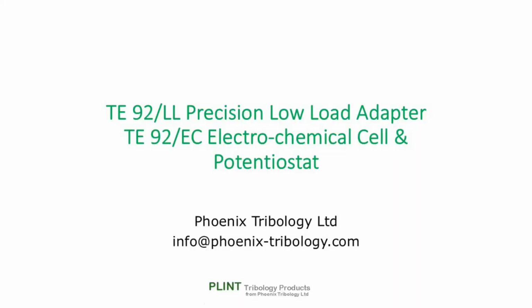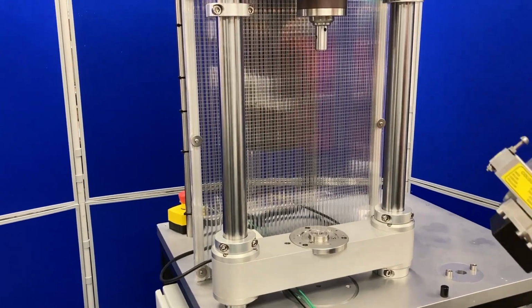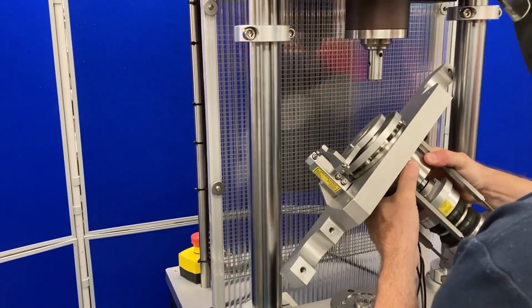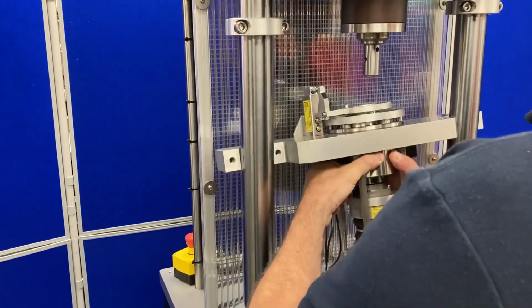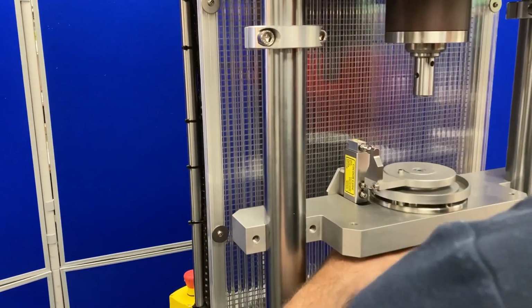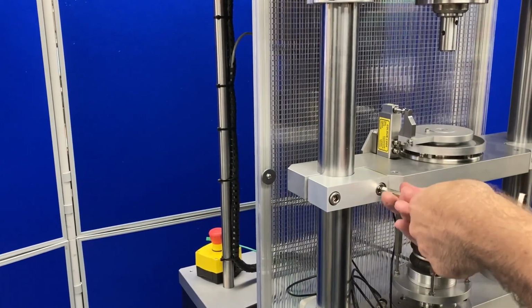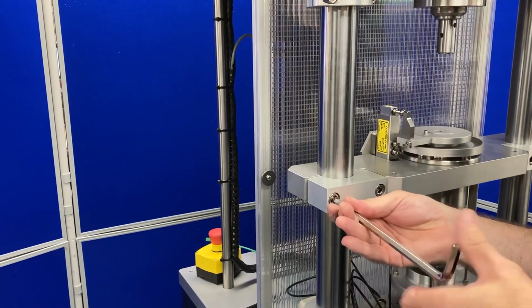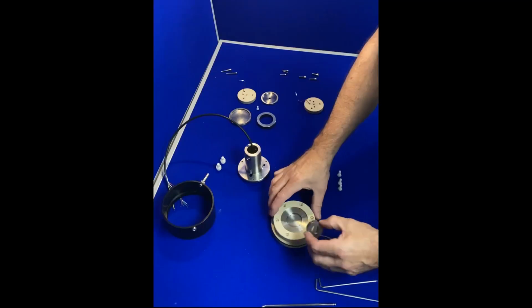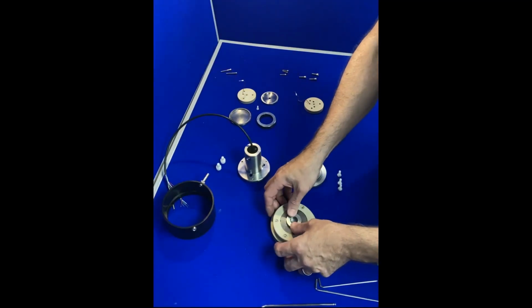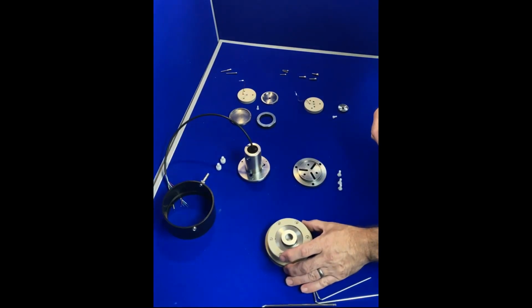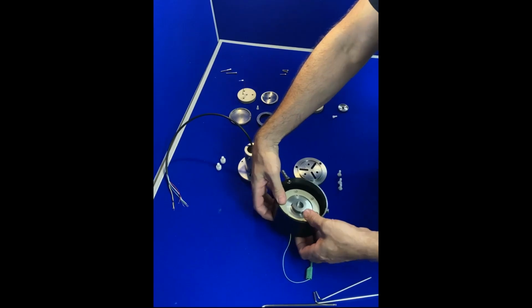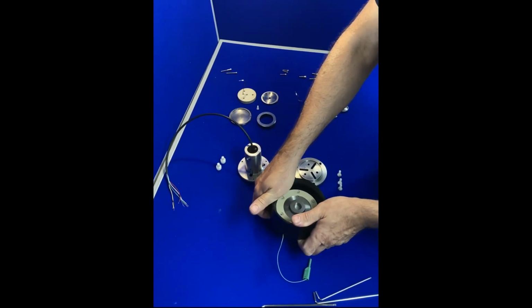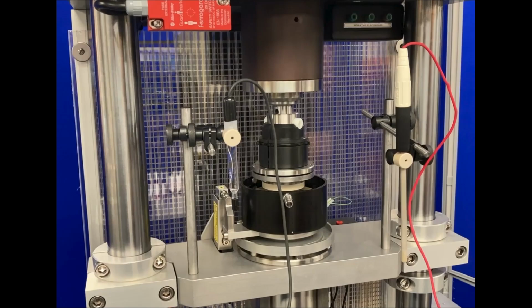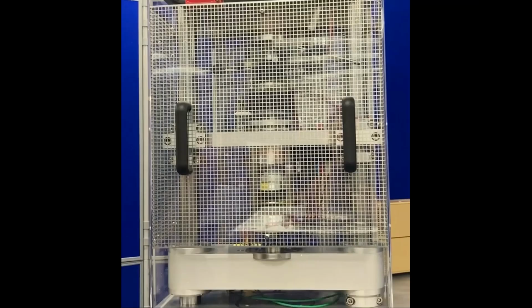A precision low load adapter is available, extending controlled load down to approximately 1 Newton axial force. This is typically used in conjunction with an electrochemical cell. The low load actuator incorporates an air bearing. The machine is equipped with a potentiostat and is fitted with a Faraday cage.